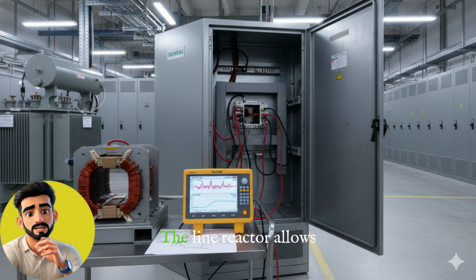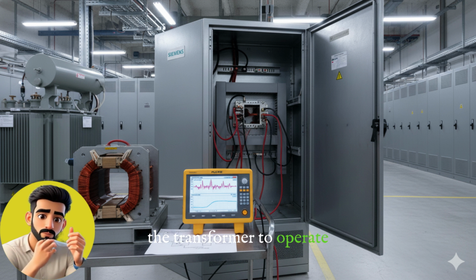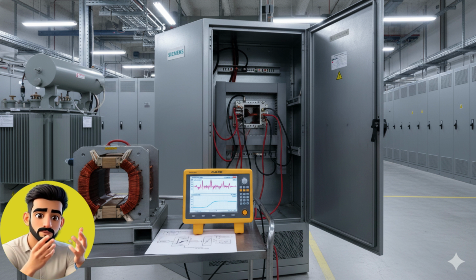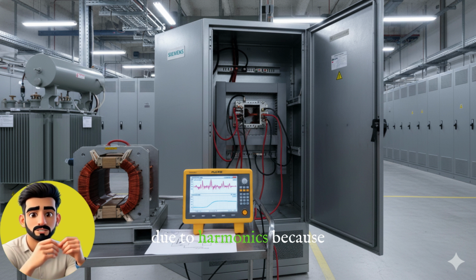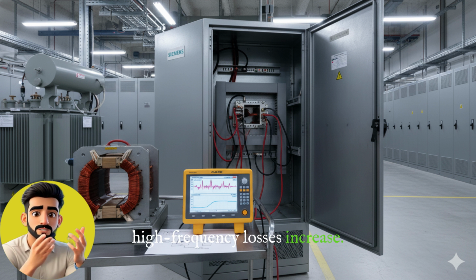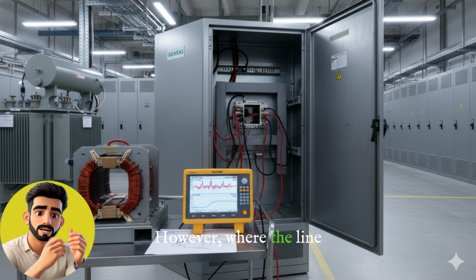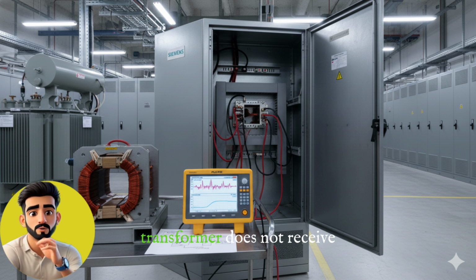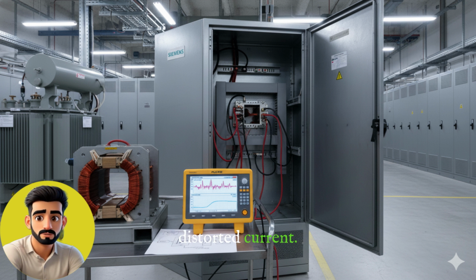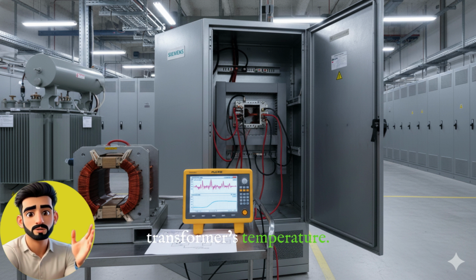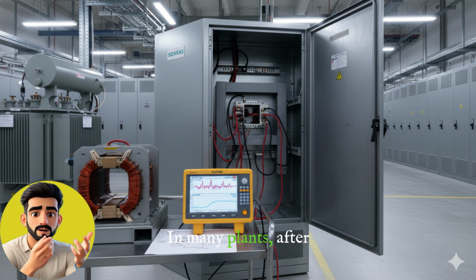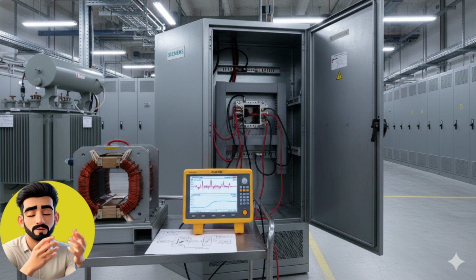Second point. The line reactor allows the transformer to operate within the comfort zone. The transformer heats up due to harmonics because high frequency losses increase. However, where the line reactor is used, the transformer does not receive distorted current. It receives filtered, smooth current. This significantly reduces the transformer's temperature. In many plants, after installing a line reactor, the oil temperature drops by 10 to 20 degrees.